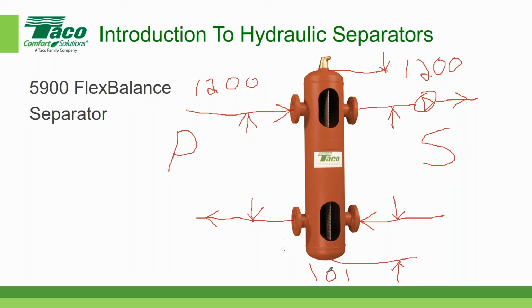And all of these things have to be taken into consideration when you design a pre-engineered product for the flow that you're looking for. There's also a baffle inside there to ensure that, in most classic examples, the flow on the secondary side will be less than or equal to the primary side, which we showed a couple of reasons why you might want to make sure that happens. In that case, we want to make sure that if the secondary flow is less than the primary flow, then you'll get some flow in this direction across the separator like that. So that is a pre-engineered hydraulic separator. It has an air vent at the top. And it's called a Flex Balance 5900 Flex Balance separator.